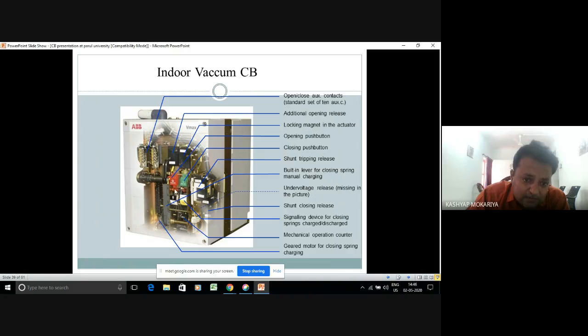So this spring charging mechanism has two parts. One is a manual spring charging by handle, and second is by means of a motor operation. Now, once you start your motor, a servo motor or any motor, with a 110 volt DC supply suppose, with your close button, then immediately you will find that these springs are charged, and it will be in a ready position to operate. Ready position means either you can close the breaker or you can trip the breaker. So all these assemblies, the counter operation is there.